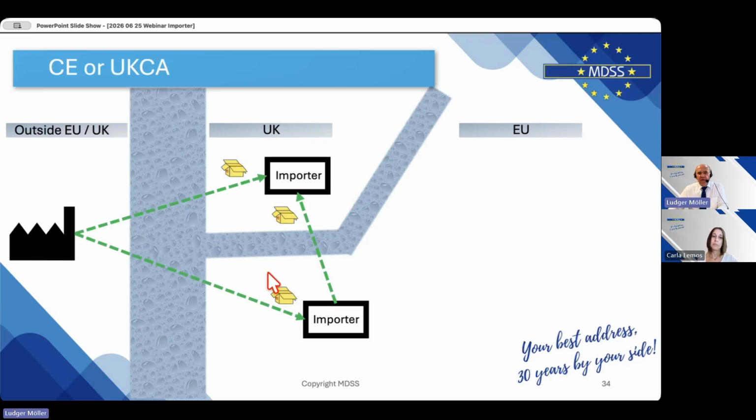Manufacturer sells this product to this entity, and if it's from the European entity here, the EU channel, being sold to somebody in the UK, then that is an importer. He would be the importer from the manufacturer directly as well. But again, not a problem at all. That's actually a blessing. And in the UK, we don't have any such requirements specifically there yet, but normal aspects apply. This entity would have to inform us as UK rep to inform the MHRA database of his existence.